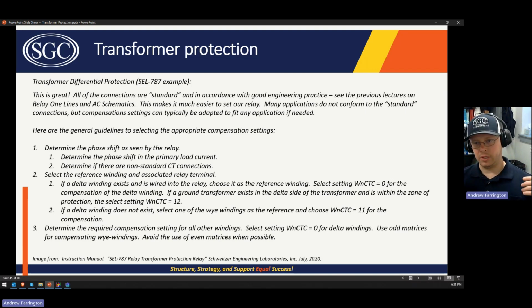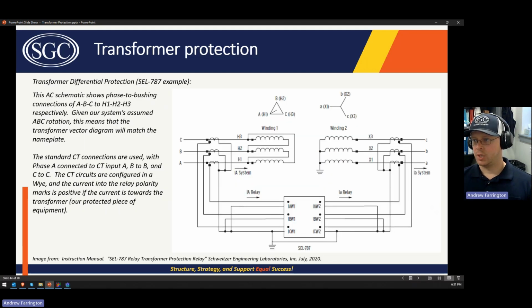So what's the difference? The setting of 0 does not remove the zero sequence current from the current going into the relay. A setting of 12 does. Why would you use one versus the other? If you had a grounding transformer between these CTs and the transformer winding, and you had a single line to ground fault over here, that grounding transformer would source fault current through those CTs. But the fault is external to the zone of protection, and it's obviously not going to be seen by the low side CTs because the zero sequence current can't flow out of this delta. It's only sourced by that grounding transformer. So you need to remove that current from the differential calculation, or you're going to misoperate for an out of section fault. So 12 removes that, 0 does not.